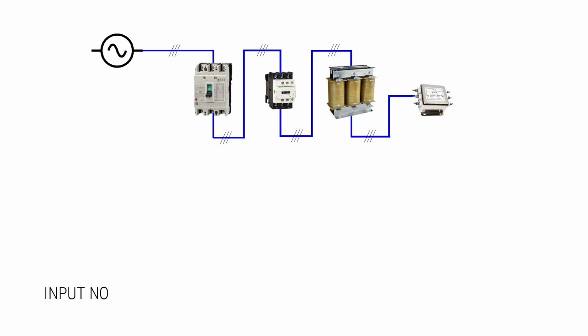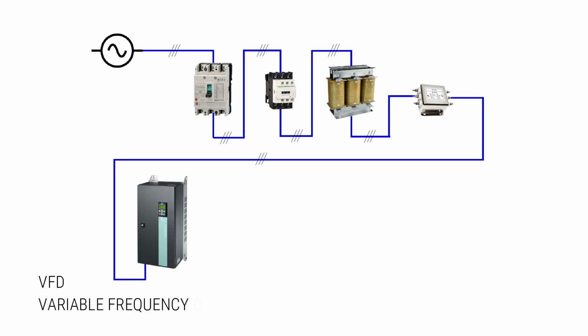Input noise filter. To comply with certain communication and interference regulations, input noise filters are to be installed. Many manufacturers include these filters. Variable frequency drive. Wire input to terminals L1, L2 and L3 for three-phase input. Make sure to connect the ground terminal to an appropriate safety ground.